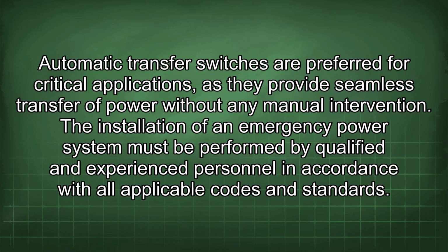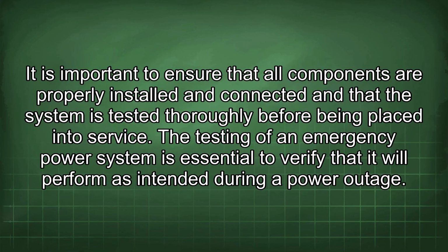The installation of an emergency power system must be performed by qualified and experienced personnel in accordance with all applicable codes and standards. It is important to ensure that all components are properly installed and connected and that the system is tested thoroughly before being placed into service. The testing of an emergency power system is essential to verify that it will perform as intended during a power outage.